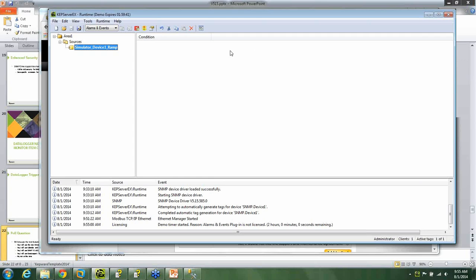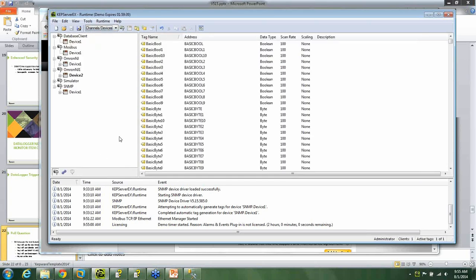So there's that option. The other option you have is simply send real-time data up to your client, and a lot of HMI and client software supports the evaluation of alarms. There's software called Win911, which uses an OPC DA or OPC real-time connection to consume real-time data and then evaluate alarms on the client level. So that's the type of software that you could use to do alarm evaluation. And simply because we don't support it in OPC UA doesn't mean that you can't get to that data.